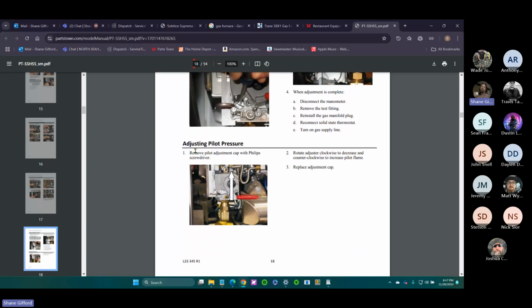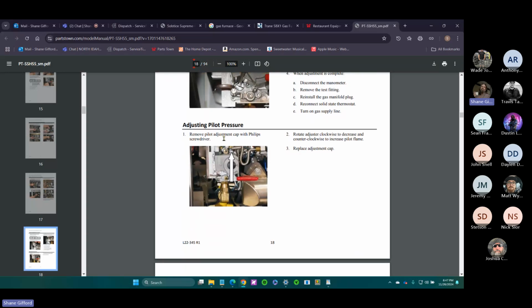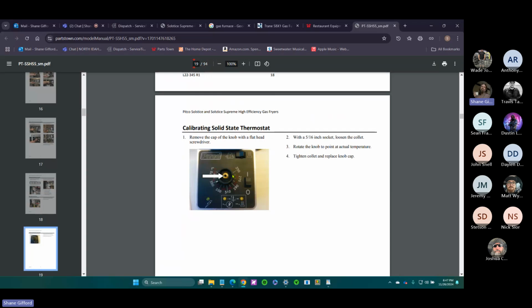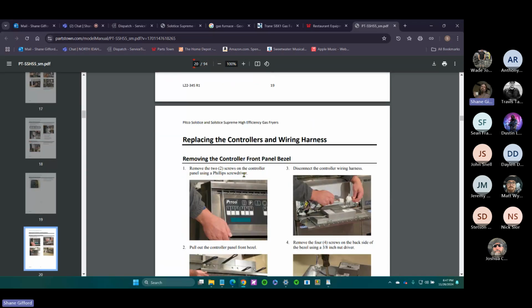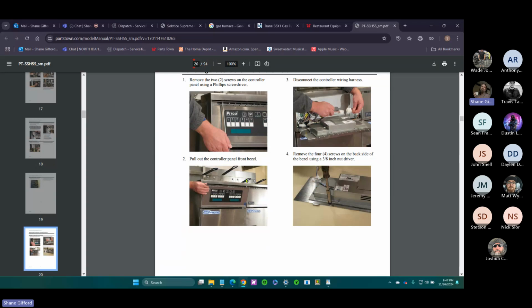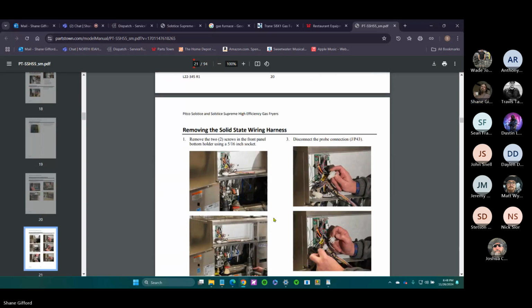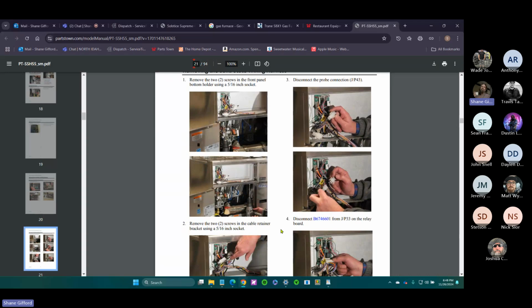This one right here, you can adjust your pilot pressure, and same on the other ones too. You don't want your pilot to be underfed or overfed; that's going to be a problem. These things require pretty much dead-on pressure. If we're saying run that pilot flame at 1/2-inch water column, then you better run it at 1/2-inch water column, or you can expect problems down the road.